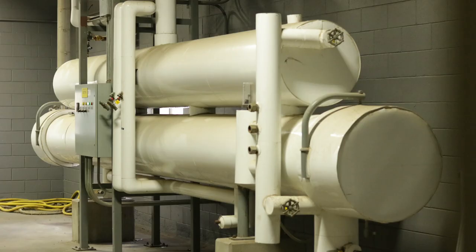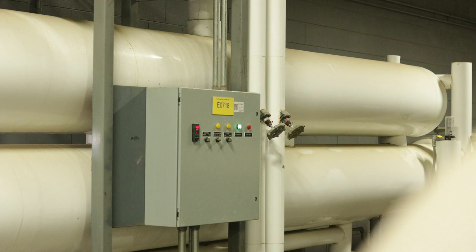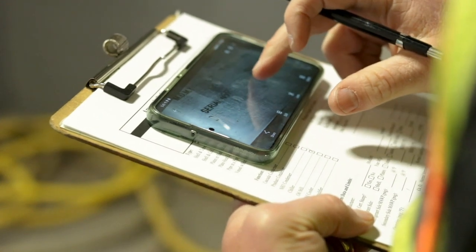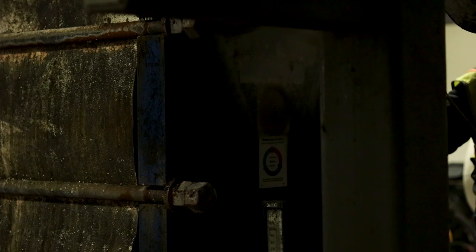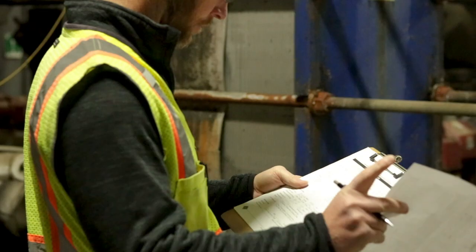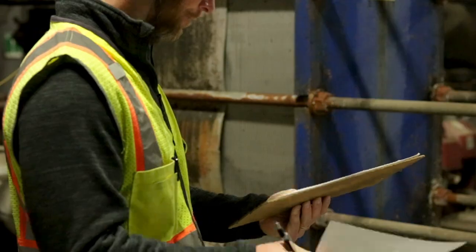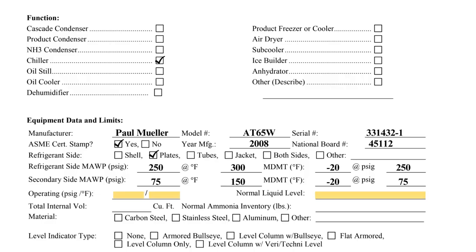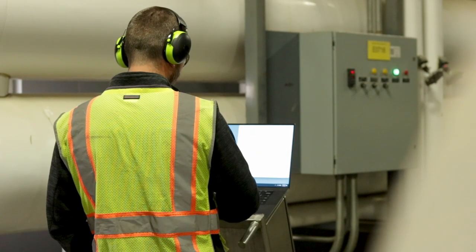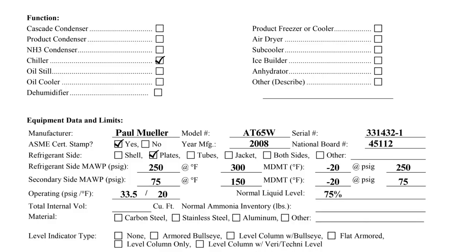In this shell and tube heat exchanger, the MAWP and MDMT can be obtained directly from the nameplate. Because the plate and frame nameplate is partially covered by ice, we use the U1A to find some of the required information. The operating pressure, temperature, and normal liquid level will vary from heat exchanger to heat exchanger and will require operator input or design information about the system.